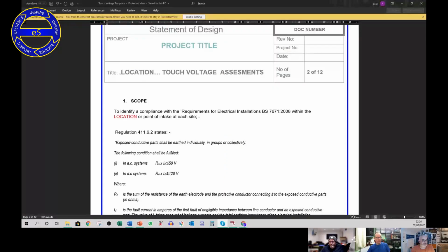Can I show everybody what I used to do for projects with regards to touch voltage? This is a commercial industrial model. If anybody watching this on YouTube wants it, they can have it. I'm going to share the screen. This was a generic pro forma that we developed to demonstrate compliance with what was Regulation 411.6.2, that said exposed conductive parts shall be earthed individually, in groups or collectively. The following condition for 50 volts AC or 120 volts DC shall be met.